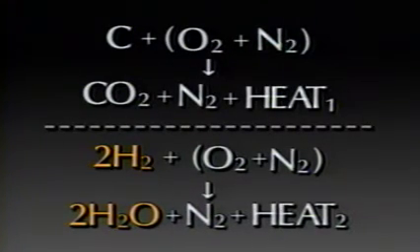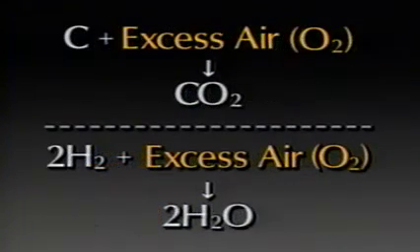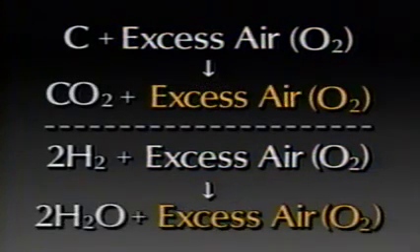But unlike this theoretical result, the actual combustion process in a burner uses excess air, also called reserve air. Excess air is readily available and provides sufficient oxygen to make sure that the fuel oil is completely burned. After the burning, there's excess air left over.